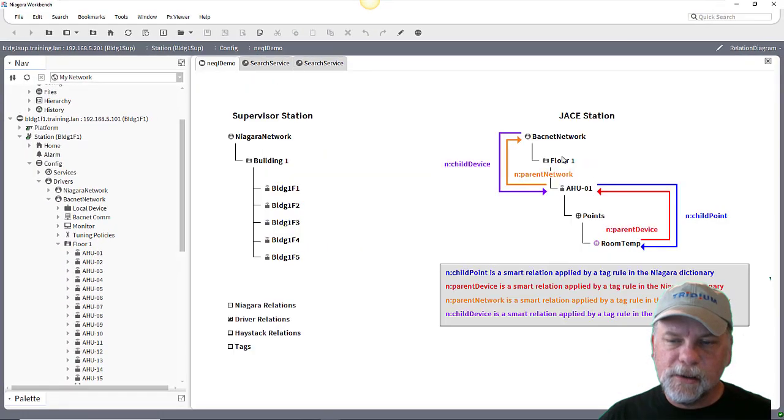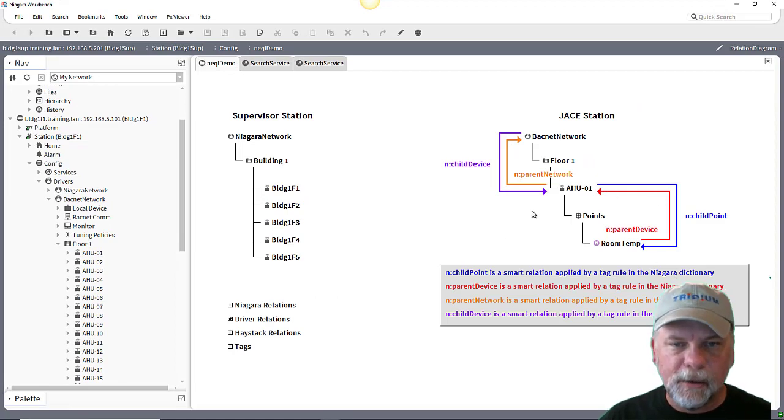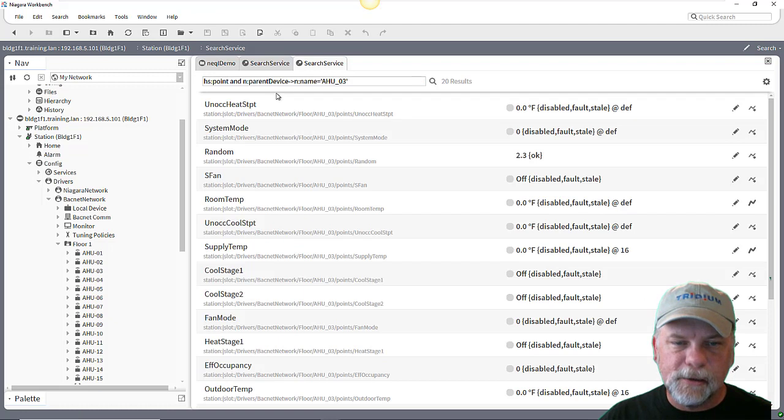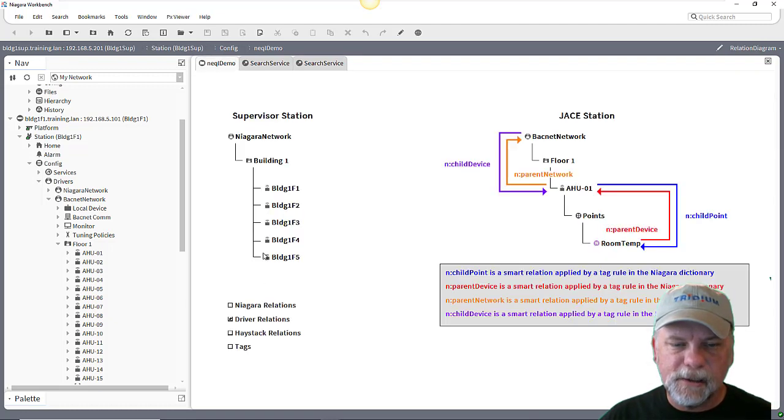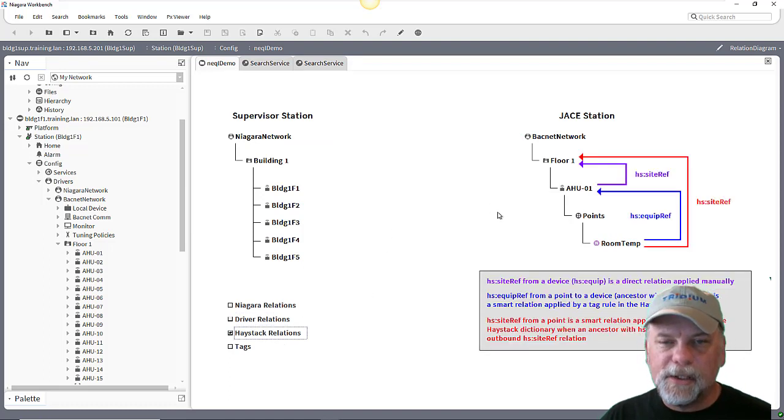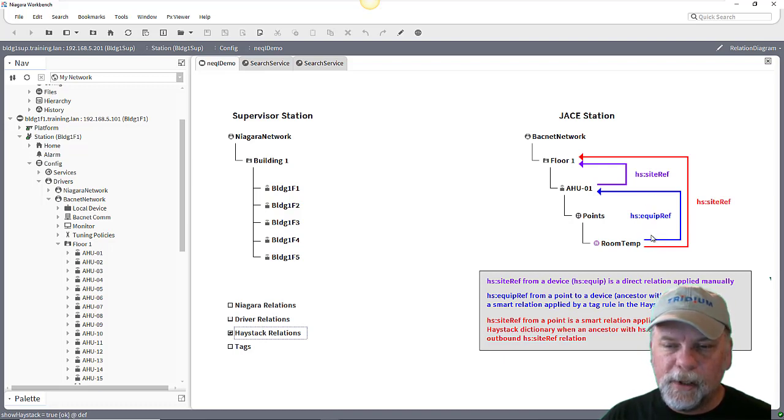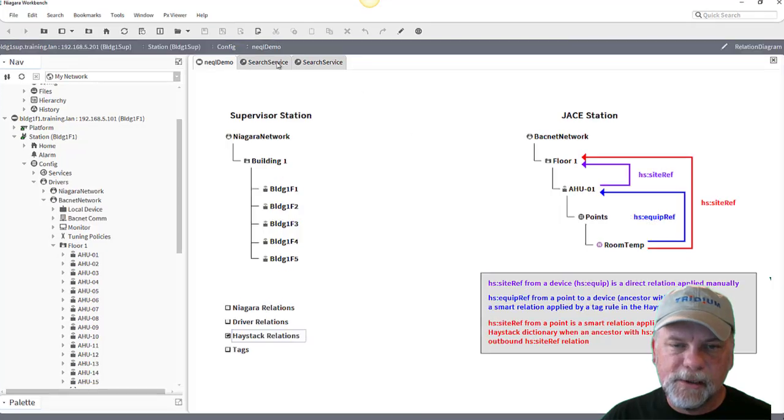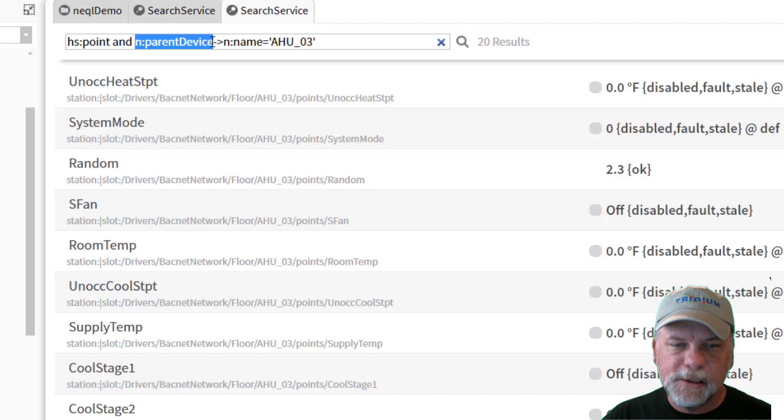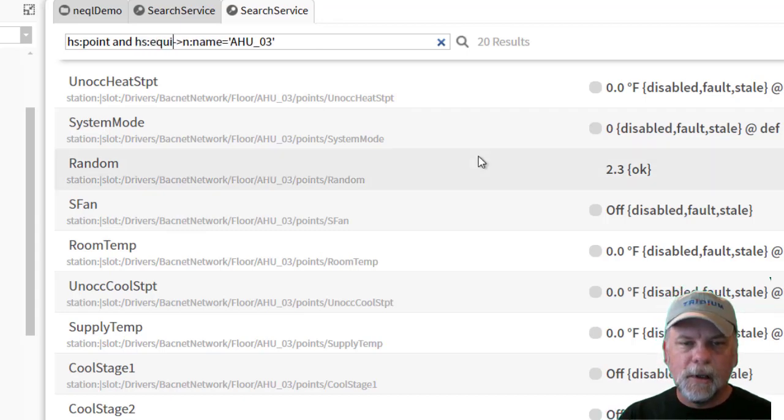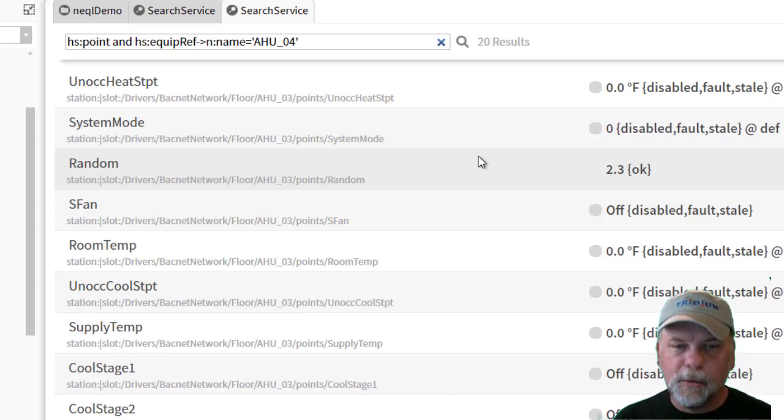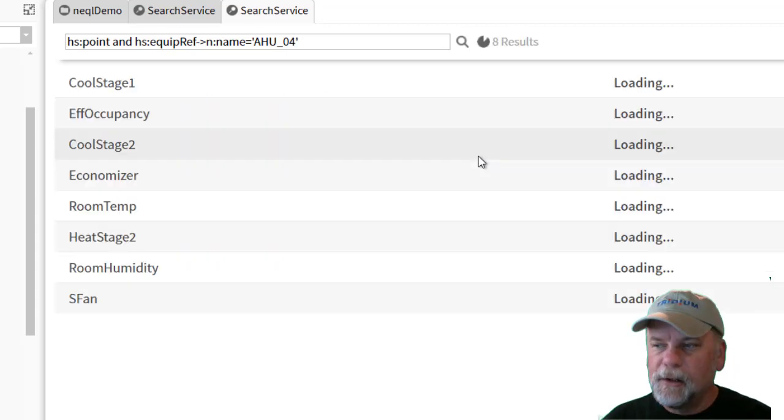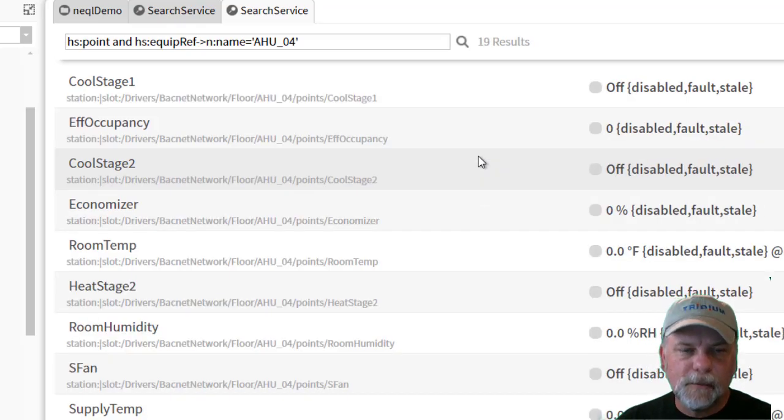We could also leverage the reciprocal n colon child point as an inbound relation just like I showed on the previous example. I don't think there's much need to maybe do that. We could also potentially use the haystack relations as well. So I have an outbound hs:equipRef relation going from the point to the device. So over here instead of the Niagara parent relationship, if I wanted to I could use the hs:equipRef relation and tell it to look for the points under air handler four and it finds all those.